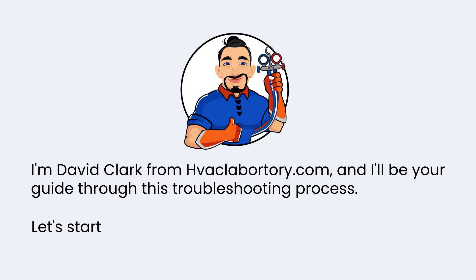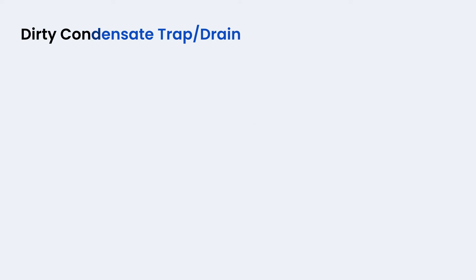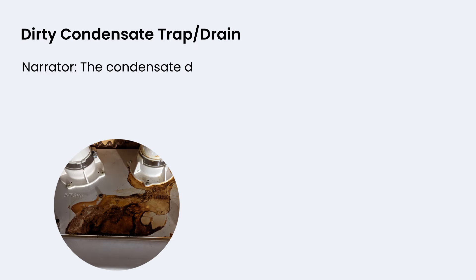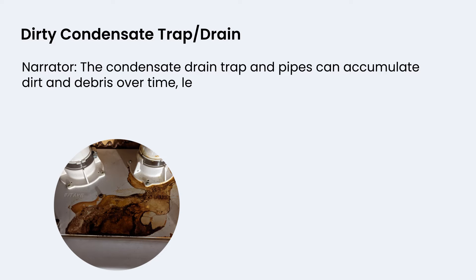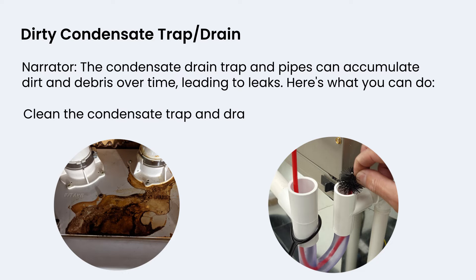Let's start by understanding the common causes and their respective solutions. Dirty condensate trap and drain: the condensate drain trap and pipes can accumulate dirt and debris over time, leading to leaks. Here's what you can do: clean the condensate trap and drain regularly to prevent blockages.